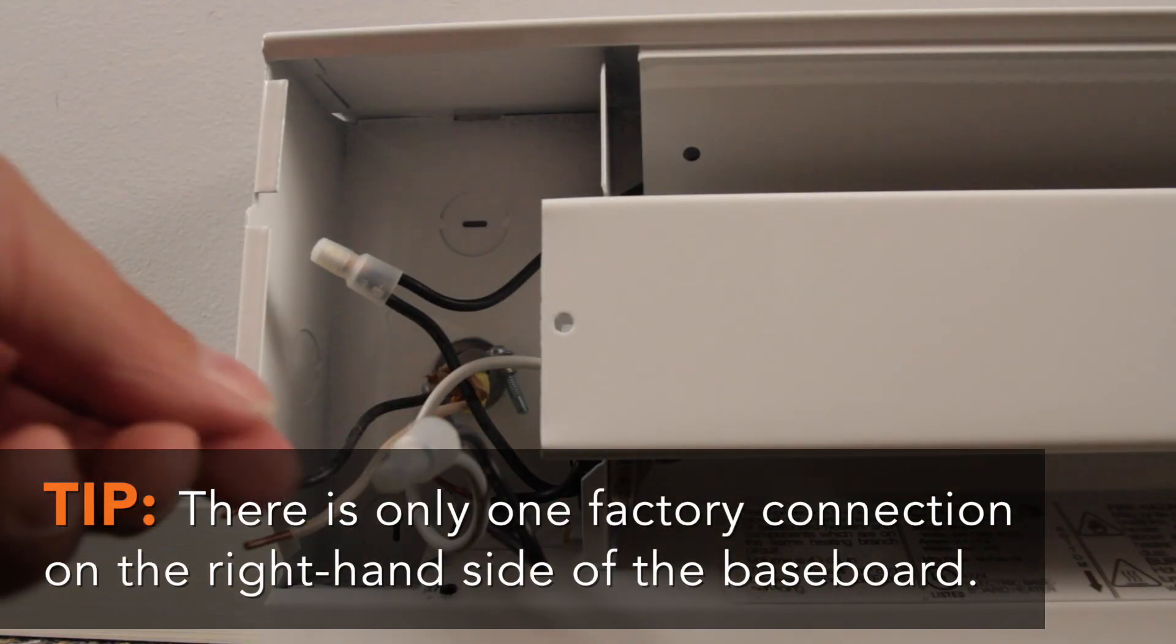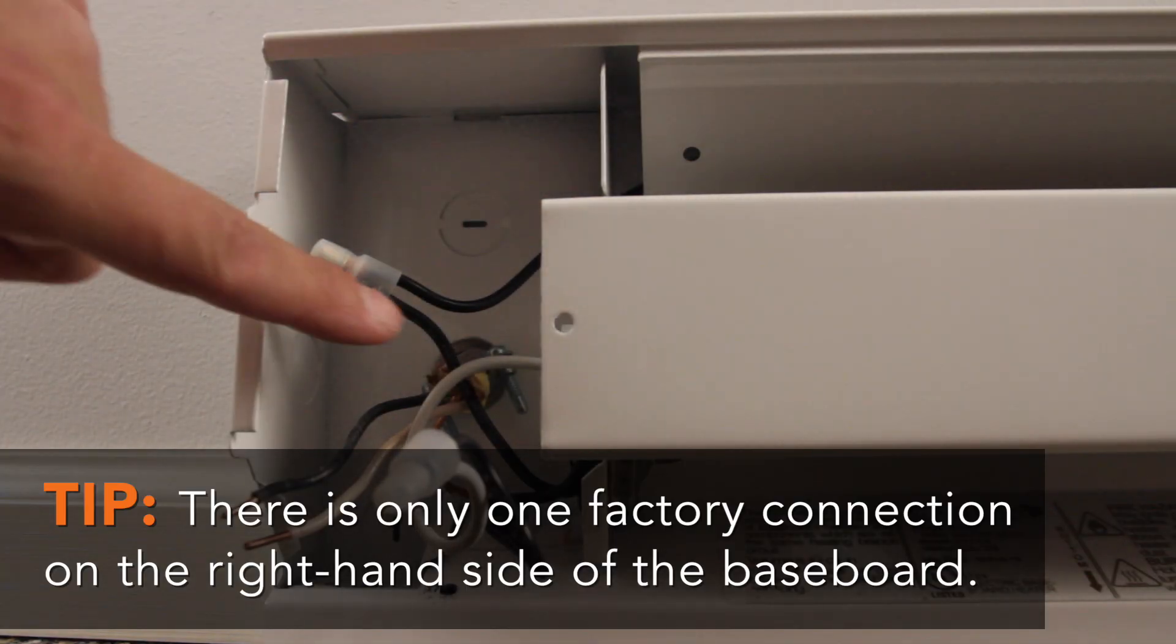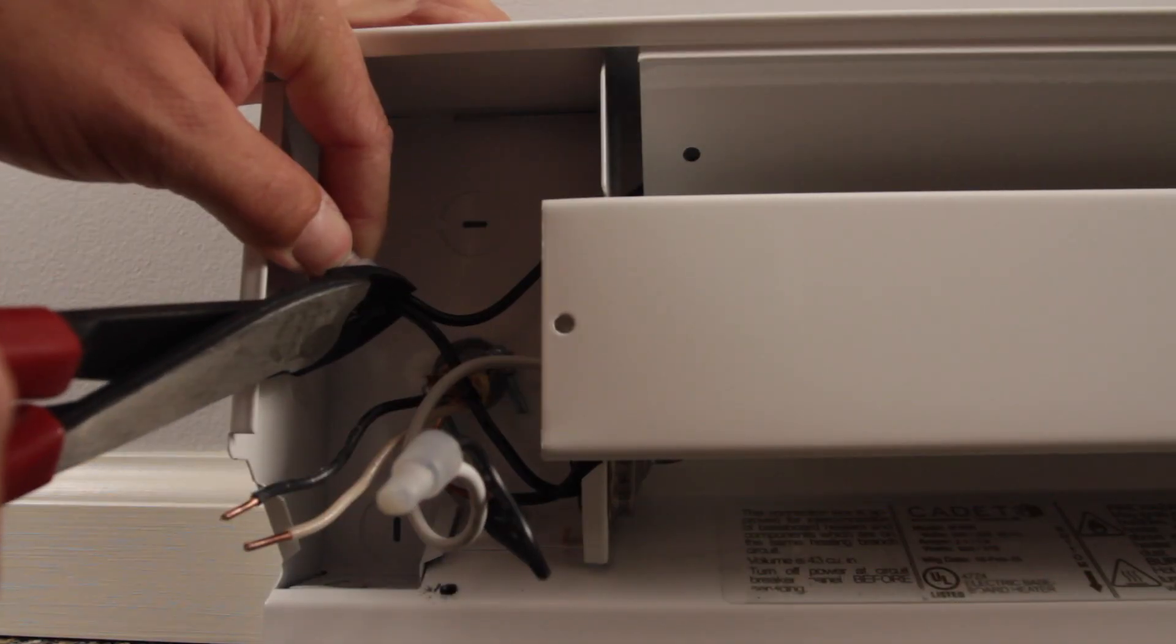If you haven't already done so, attach your bare copper ground wire to the green ground screw. There are two factory connections. Find the one that does not have the white wire. Cut that factory connection.